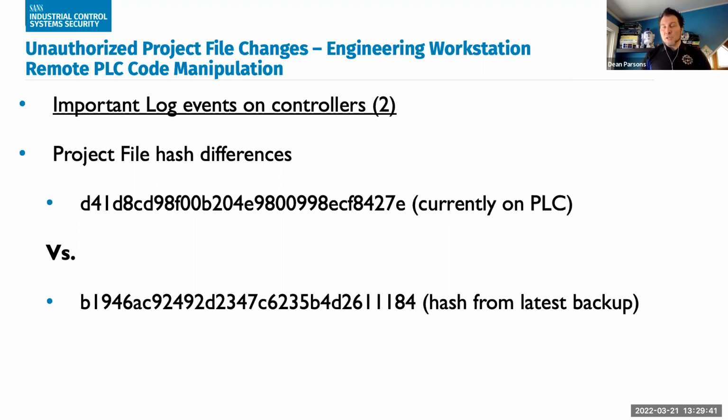And at this particular point, if you are only left with this hash, which are different, you may have to get your engineering folks more involved. There may be manipulation inside the PLC code, and that requires obviously reading the project file and so on. So again, engineering folks will be needed likely for this particular phase.